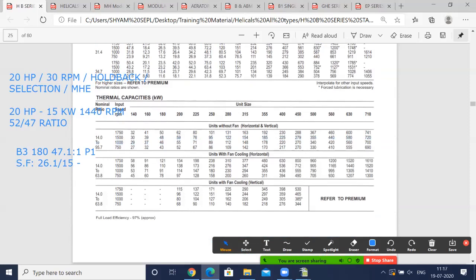So what do we learn? In high speed gearboxes where the ratios are low, the fan and other cooling options are required. As the ratio increases, the speed decreases, the heating of the gearbox decreases, and we don't require a fan. So as you can see now, in this case, we do not require a fan. Okay, perfect. That is how a selection is done.